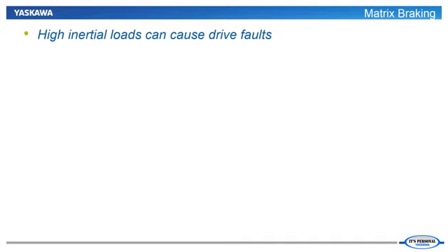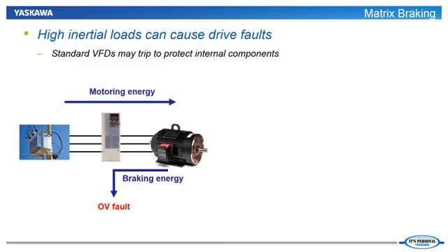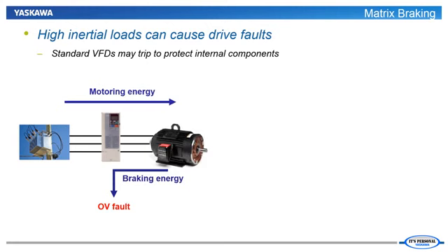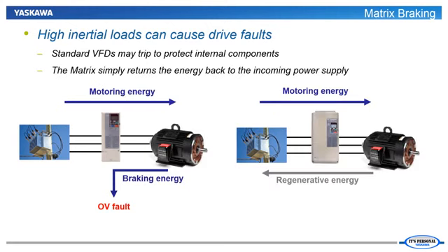Our final benefit of the matrix drive is the inherent regenerative operation of the matrix drive technology. Most fan and pump applications don't require motor braking during their normal operation. However, high inertia fans can cause a VFD to trip on an overvoltage condition as it reaches set speed. The inertia of the fan will want to keep the motor accelerating, so the VFD will need to deal with the regenerated energy. This causes a regenerative condition which sends energy from the motor back to the VFD, causing the overvoltage fault. The matrix drive with its bidirectional switches will automatically send this regenerative energy back to the line for tripless operation. The matrix is also helpful to prevent OV faults caused by large supply fans overhauling smaller return fans. Everything necessary for regeneration is built right into the Matrix.